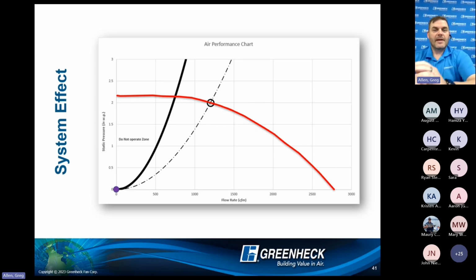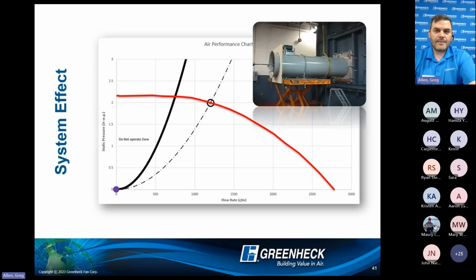So in our scenario here, this is exactly what we ordered. We ordered 1200 CFM at 2 inches. It was a beautiful curve. It was at an efficient point of operation in this fan's capabilities. Perfect. That's how I tested this fan. That's how I got all this data. And mind you, air moves into the fan beautifully smooth. It exits beautifully. Everything's gorgeous.